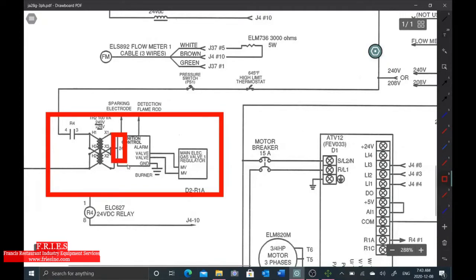Either I have 24 volts here constantly, okay. If I have 24 volts here constantly, but I'm not getting voltage here, that means the module's in lockout. We have not detected the flame. If I do not have voltage here, I'm going to work upstream. I'm going to work backwards and try to figure out what happens, okay, how this module resets.